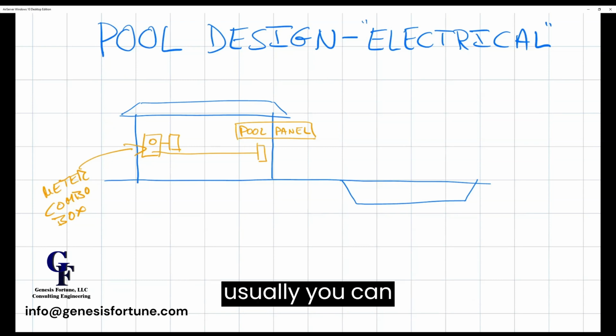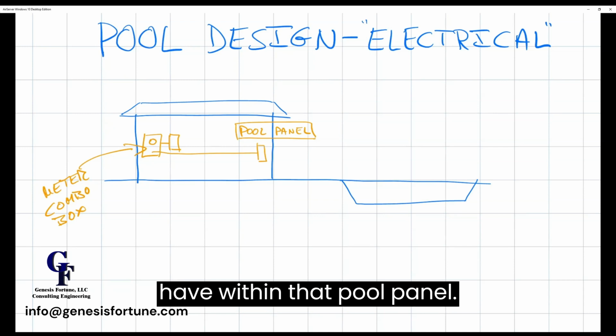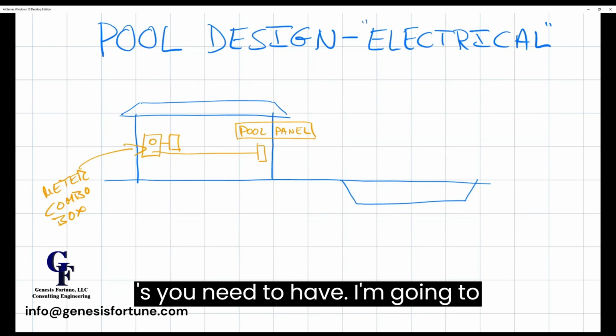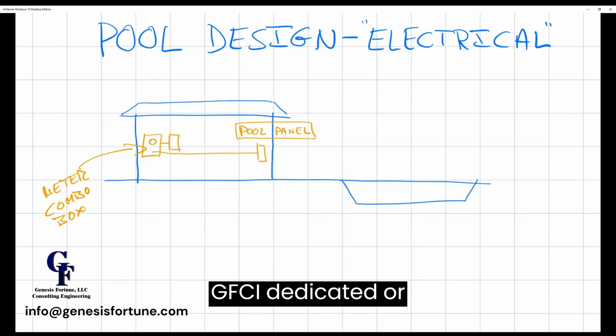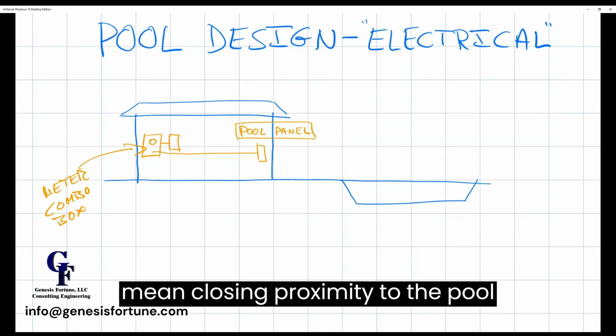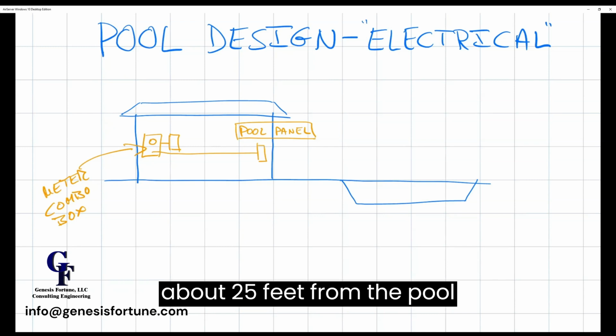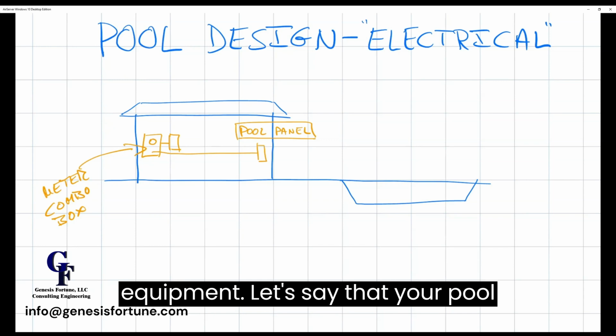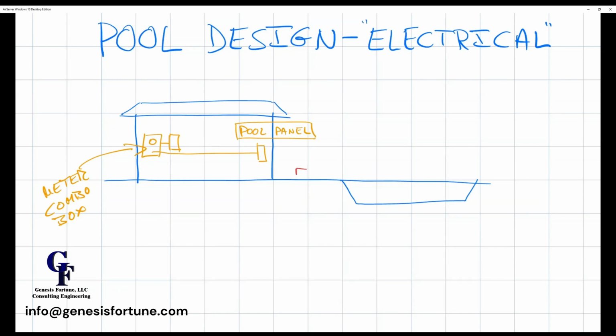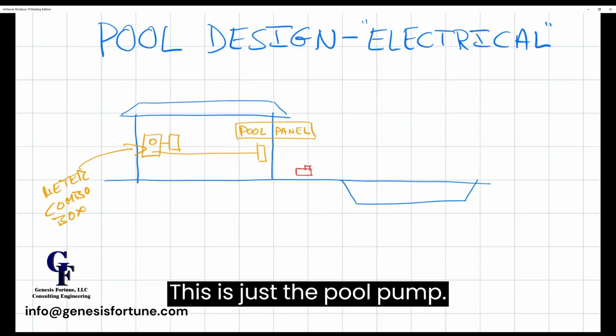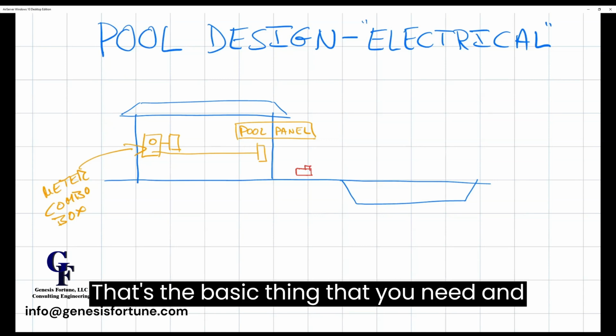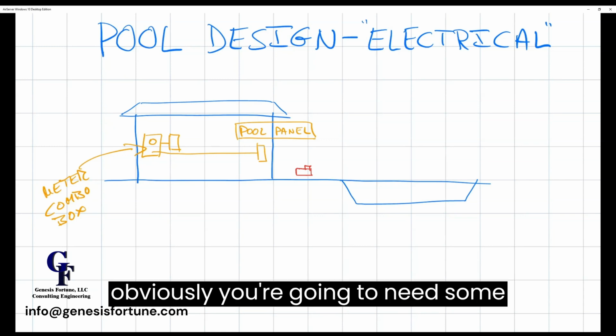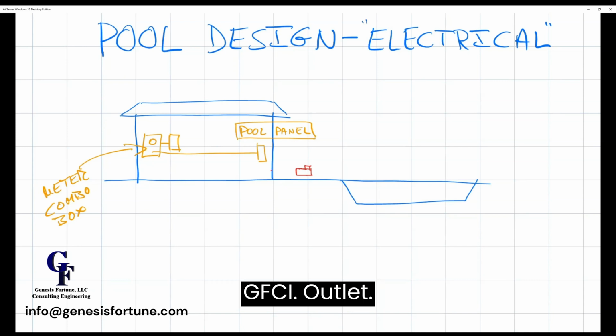So what usually you can have within that pool panel is a connection to the GFCIs. You need to have one, I'm going to represent it in red, dedicated, or close in proximity to the pool, about 25 feet from the pool equipment. Let's say your pool equipment will be right here. This is just the pool pump. That's the basic thing you need, and obviously you're going to need some lights. You need a GFCI outlet within 25 feet of your pool equipment.